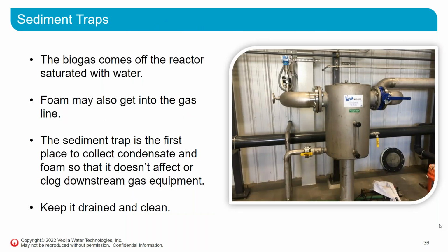So first off, we have sediment traps. Pretty much any biogas system you'll see will have sediment traps. Biogas comes off the reactor at the particular temperature and pressure that's in the reactor. It's fairly saturated with water, not necessarily a high quantity, but you definitely have a presence of water vapor. So the sediment trap will collect the condensate or any foam that may get into the gas line and prevent it from going further into the gas line, which could cause clogs, which affects your reactor back pressure.